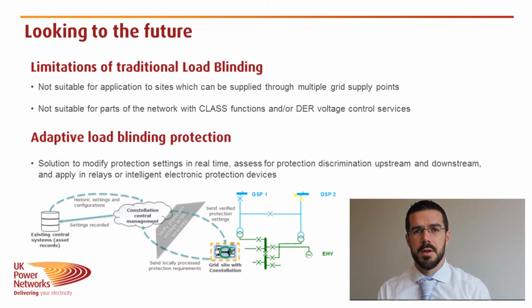So it can also be an issue at sites that are fed from multiple grid supply points with different major network configurations, because the different power flows at these sites can also cause different issues for load blinding. And so in those cases, the protection and the settings need to be able to be configured dynamically to cope with the change in the network conditions.